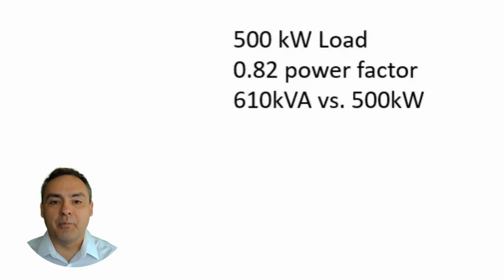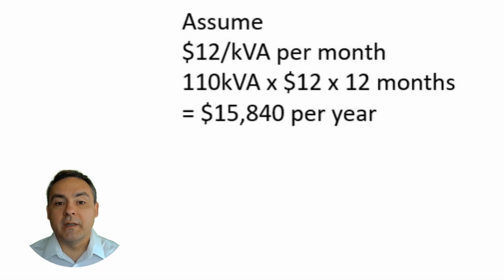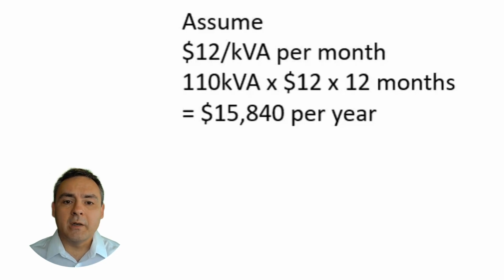Let's look at an example. A facility with a 500 kilowatt load operating at 0.82 power factor, billed on kVA demand. That means we're charged for 610 kVA instead of 500 kilowatts. If our utility's demand charge is $12 per kVA per month, that's 110 kVA times 12 times 12 months, which is $15,840 per year in excessive cost.